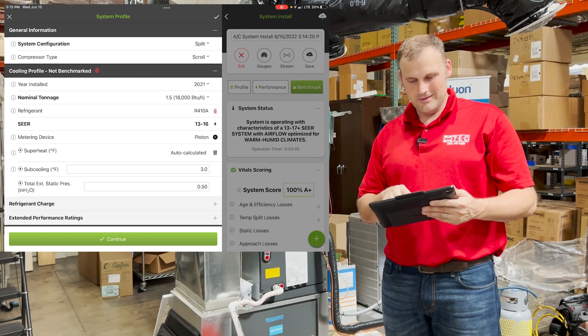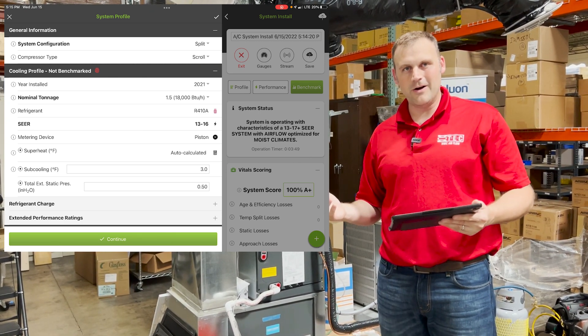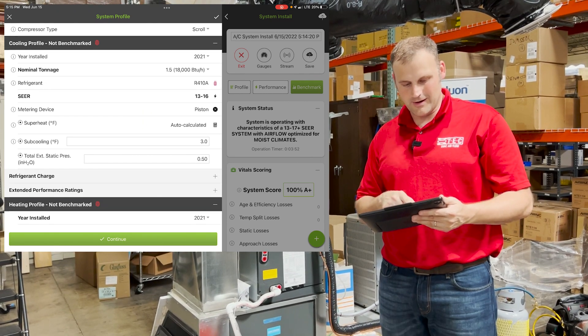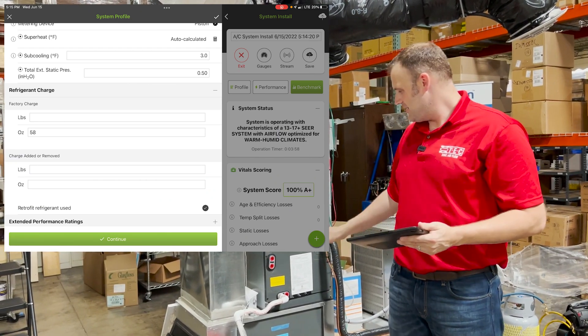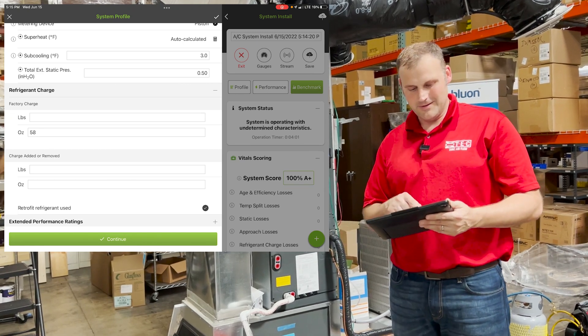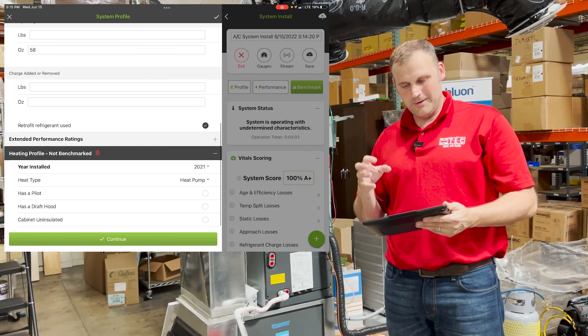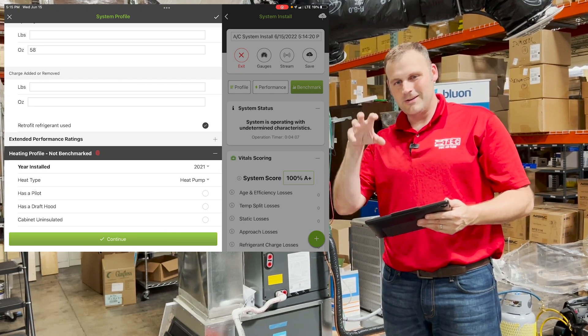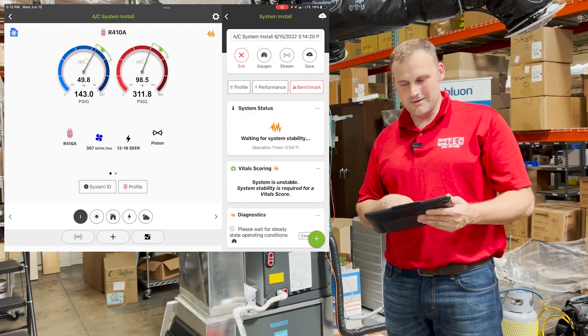It's a 13 SEER unit. It's a piston. The superheat will be auto-calculated. Our subcooling target is three. Total external static pressure is 0.5, labeled on the tag of the air handler. All that's been entered, but we're just double-checking it. If it's a new system, I'm gonna reiterate it — you have to profile it. You have to put all that stuff in. Click Continue.